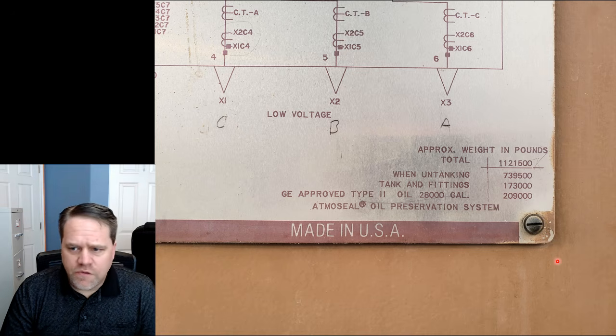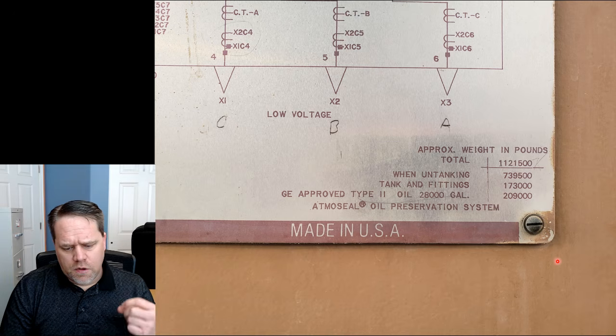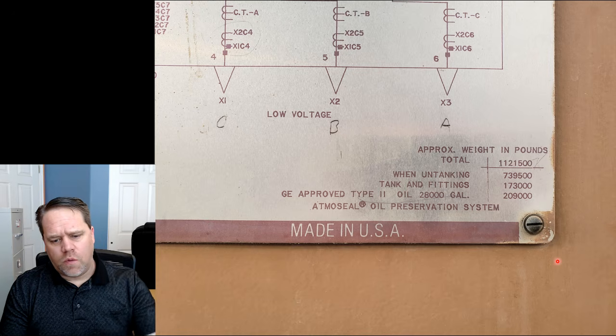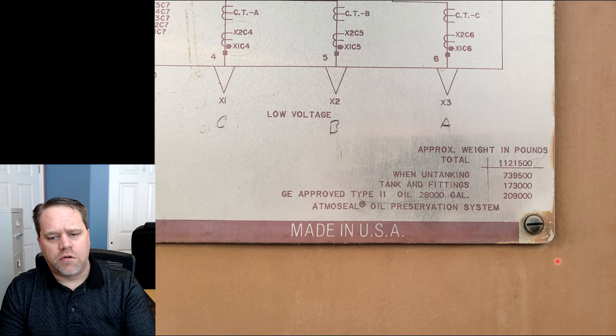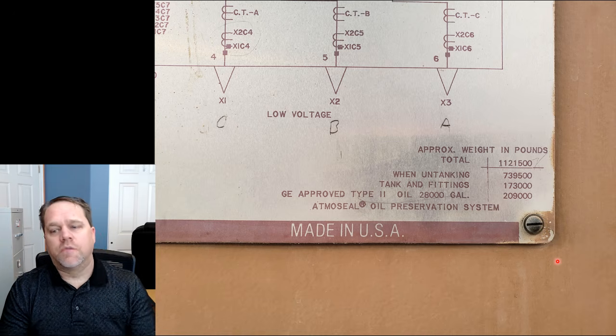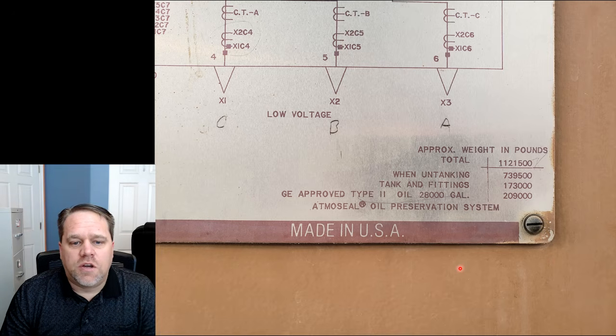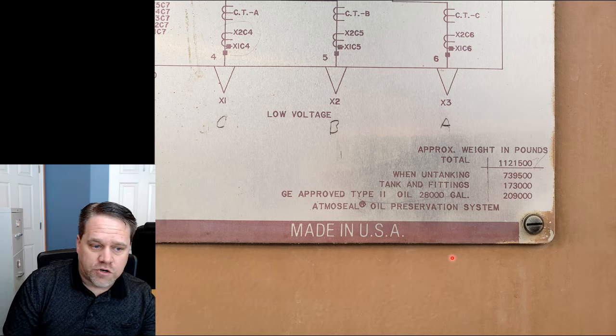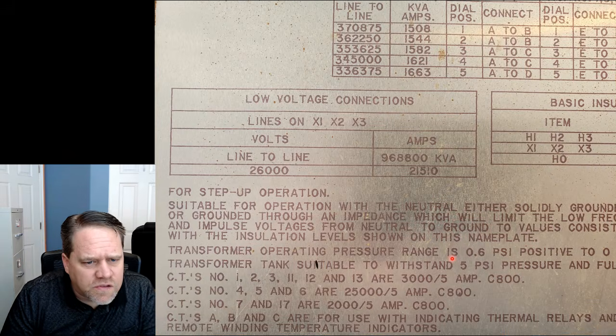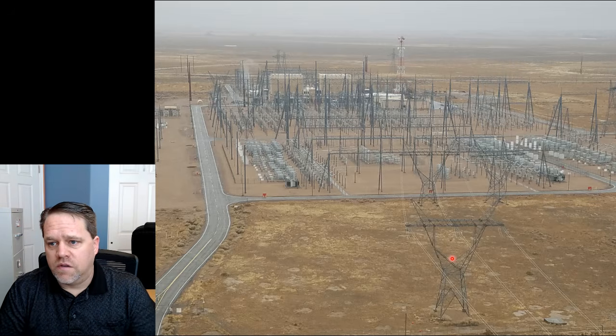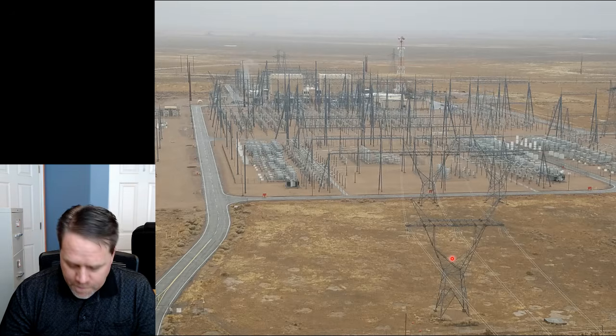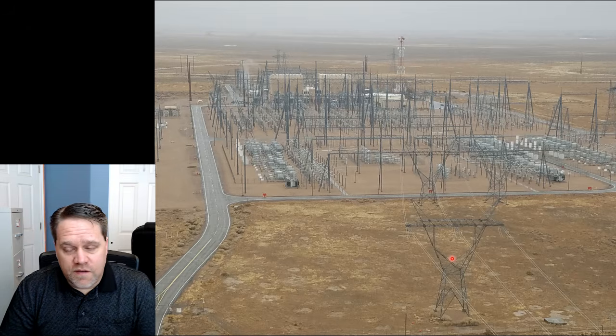So we light the coal on fire, we heat it up, we heat the boilers, we turn the water into steam, we steam the generator which creates power, 26,000 volts, 20,000 amps, and it shoots over to this transformer. The transformer changes it, because this is the low voltage side at 26,000, and it steps it up to, I believe, 500 kV. I don't have the exact high voltage numbers here, but it supplies the switch yard at around 500,000 volts. Out of the switch yard, we get into transmission and send it to different parts of the western United States. That's the process of making electrical energy.